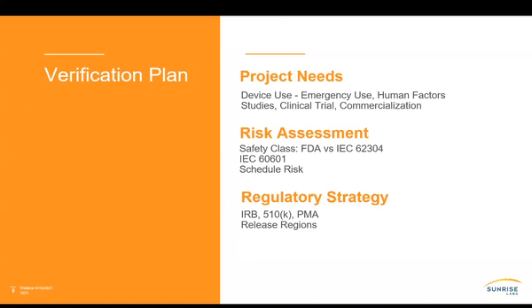Okay, and then also with your verification planning, you want to look at schedule risk. So maybe you need redundant tests or redundant resources to make sure that testing is done in the right amount of time. We'll emphasize this over and over again, but you want to overlap the verification process as much as you can with the development process. Not formal verification, but at least doing dry runs and making sure that your protocols are developed correctly and test the requirements that you need to test, that you have full coverage, and that you're not going to come up with an unexpected failure during the formal verification process.